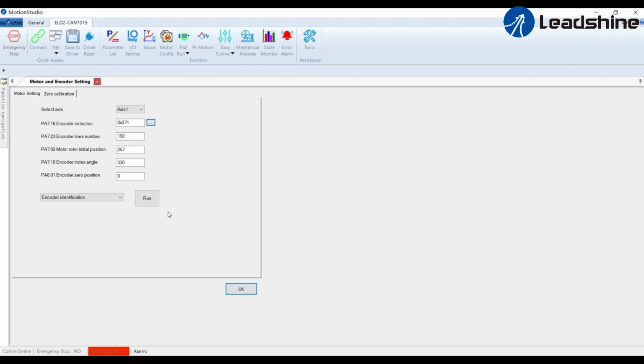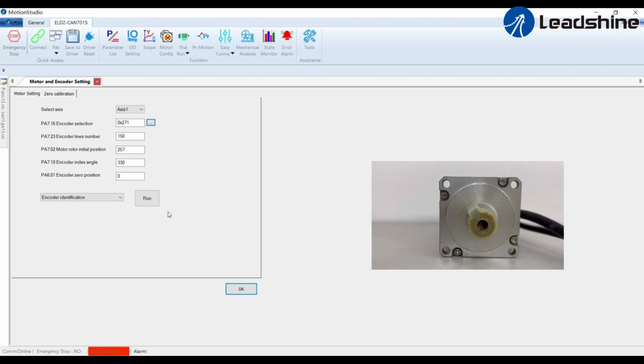If there is no alarm, select encoder identification, then click Run. The motor will begin to rotate slowly. After the motor stops, encoder zero calibration is completed.